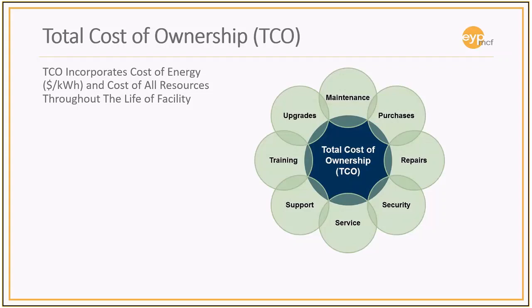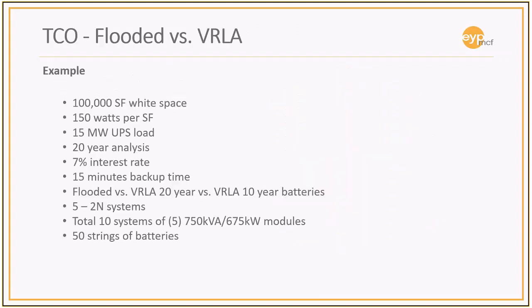And as you look at these total cost of ownership issues, we take all that into account when we're trying to evaluate one system versus another. So in this particular example, we're comparing flooded batteries to valve-regulated batteries. We're looking at a large UPS system, a large plant, the 15 megawatt UPS plant. We're looking at the 20-year life cycle of this system. We have obviously taken into account the cost of money and the backup time, and we're looking at 20-year valve-regulated batteries versus flooded cells versus 10-year valve-regulated batteries, different UPS configurations, a total of 50 strings of batteries.